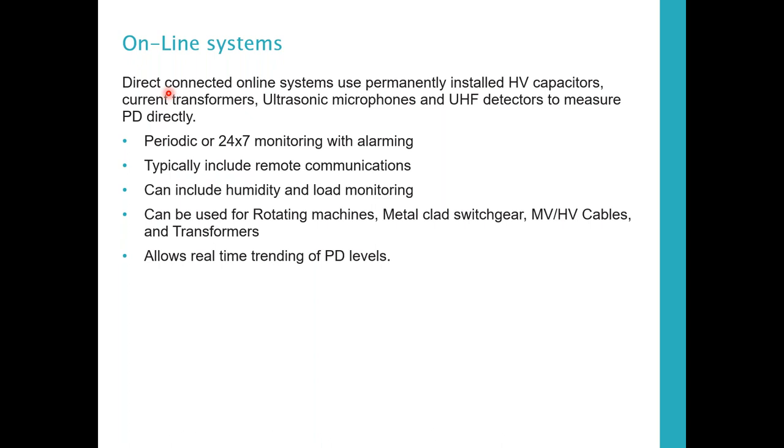It's also allowing you to collect other information like temperature and humidity. You can measure the temperature of the individual cubicles. Some of them have attachments for measuring temperature on bus bars, etc. So you can bring a lot of sensors in and monitor a system full time and now trend it. So you can slowly see it building up over time and see changes over time and get a good feeling of how severe is it, how progressive, how much has it progressed based on this information.